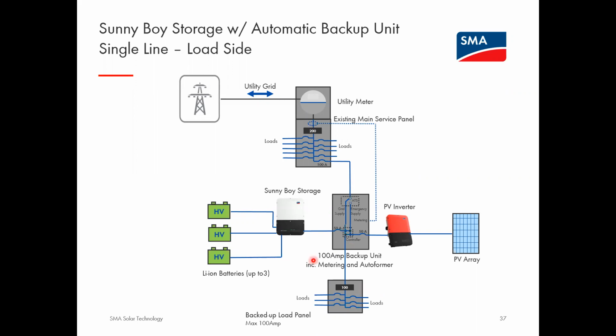And so here you would physically move the circuits that you want to back up from the main service panel to the backed up load panel. And again, anytime there's a grid outage, anything below this automatic transfer switch is able to be supplied with power from both the SunnyBoy Storage and the PV inverter. The PV inverter, of course, is capable of recharging the batteries because they're electrically working in unison. So if you're in the middle of the day, producing a lot of extra PV and the grid is down, you're still able to recharge your batteries.